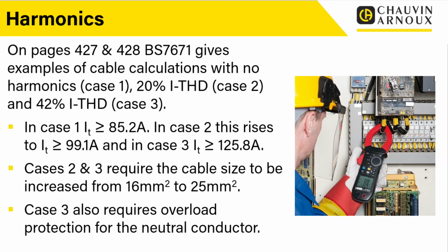So it is important. And also in case 3, because it's talking about the neutral currents, it actually requires overload protection. And this is detailed in case 3. It actually requires overload protection for the neutral conductor. So that would be an overload protection device that monitored the neutral current as well. It didn't just work on the line currents. So again, that's increased overload protection as well. So not just have we got to make the cable size bigger, we've actually got to change the protection device as well.